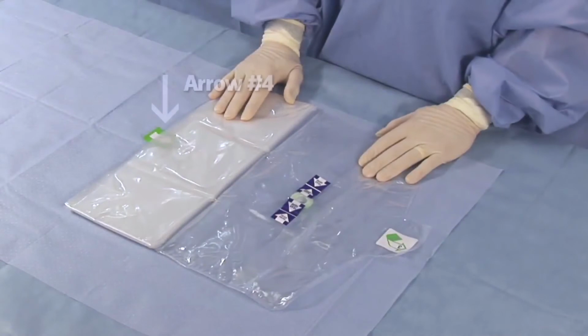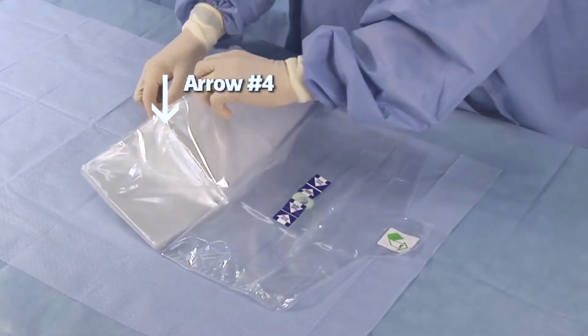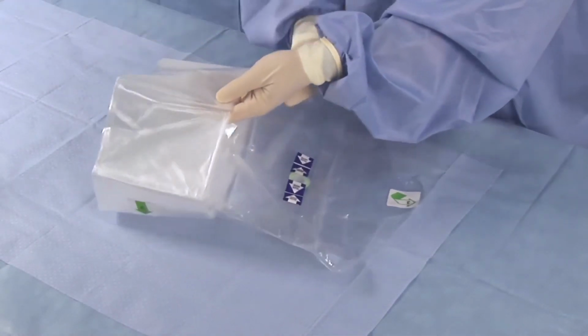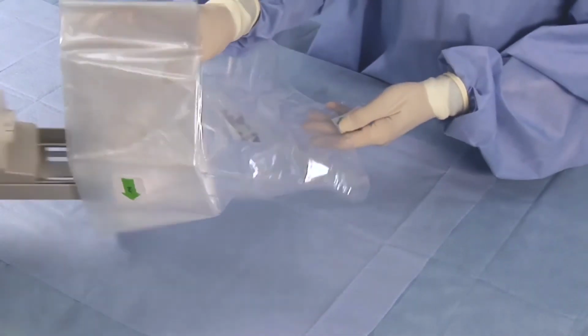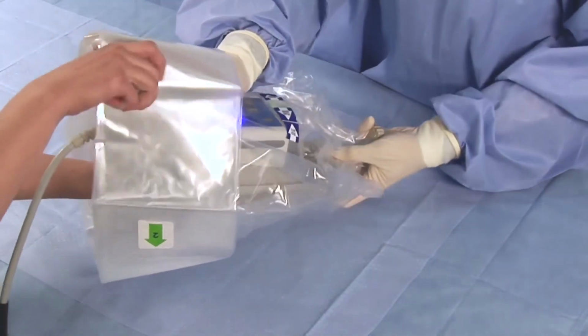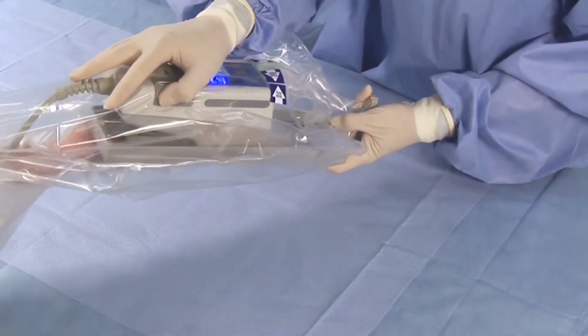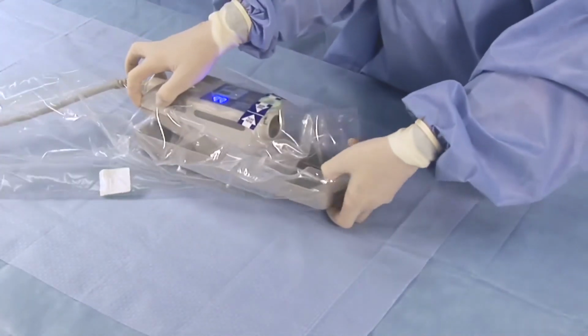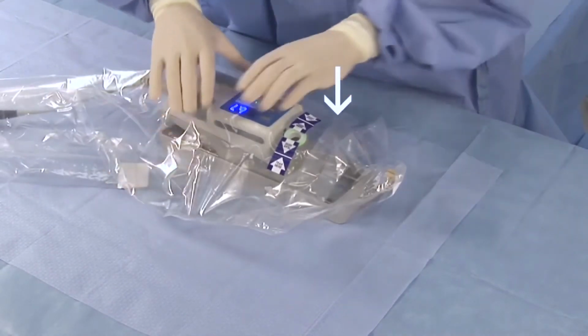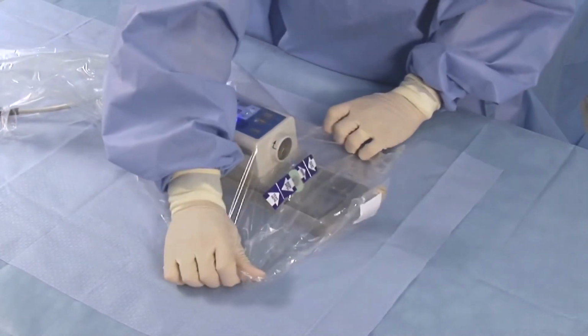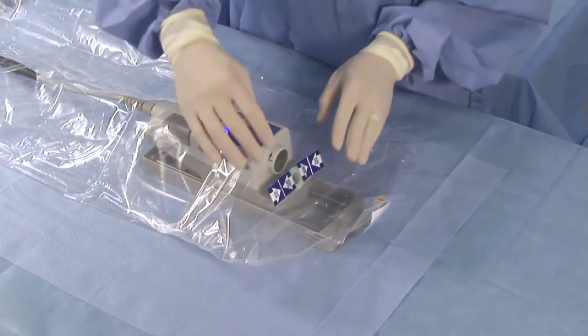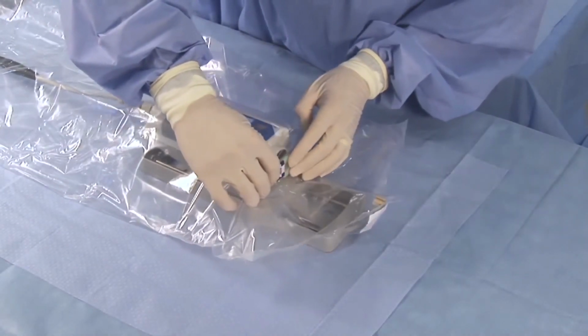Note that this step will require 2 people: a sterile person to continue handling the drape, and a non-sterile person to handle the PIM-R and cable. Locate arrow number 4. Open the fold and insert the device, ensuring it reaches the nose at the end of the cover. Pull back the large fold to fully cover the device cable. Ensure the small fold is between the device sled arm and catheter port. Place the plastic connector into the catheter port and remove the sterile barrier tape.